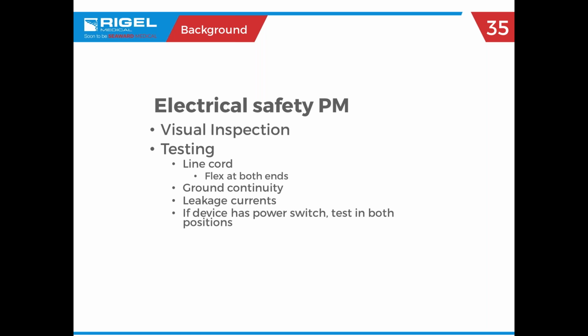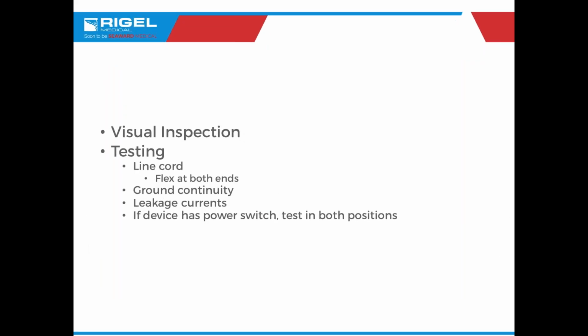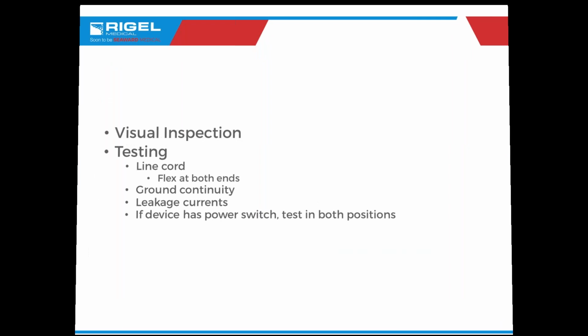So you're obviously going to start with the usual visual inspection. Just be sure there's nothing obvious to the naked eye that could affect the safety of the unit. And then you'll dive into testing. And once again, remember that every manufacturer will require different methods of testing as well. So make sure you follow that particular company's manual. So you'll start by testing the line cord, flexing it at both ends, making sure that nothing's out of place that could possibly affect your readings. Then you'd go into your ground continuity, then into your leakage currents. And keep in mind too, if the device has a power switch on, it needs to be tested in both the on and off positions. So that's pretty much the same slide.